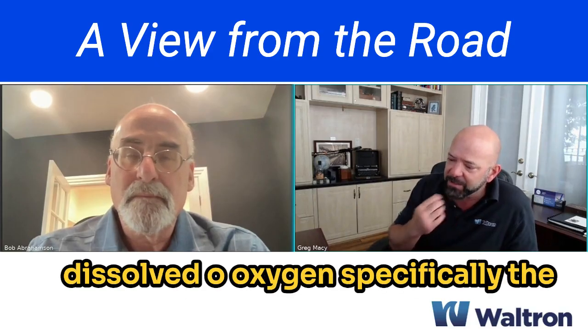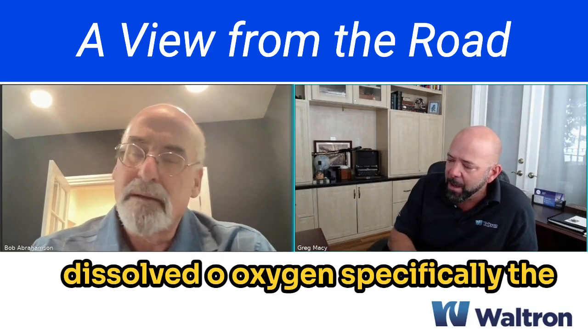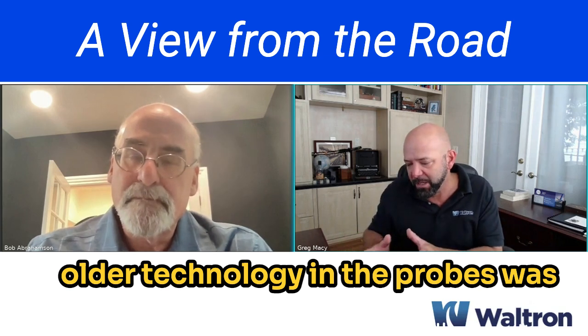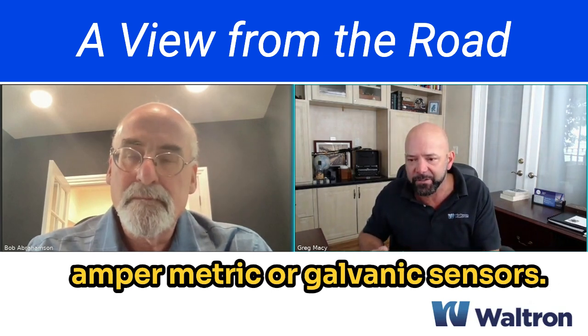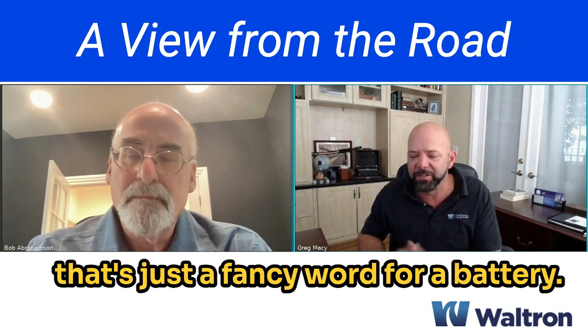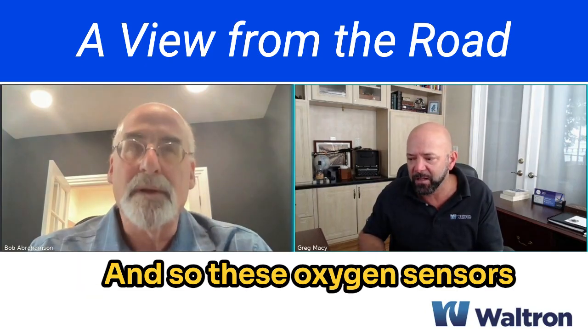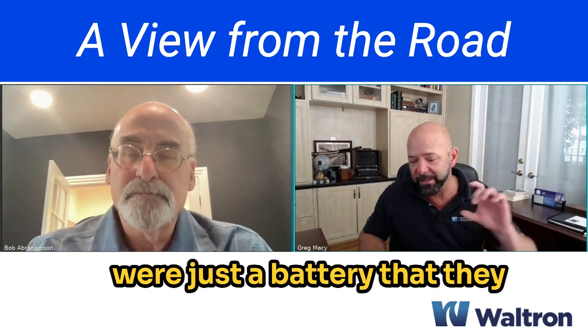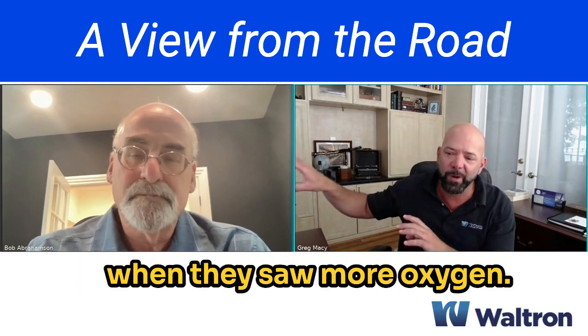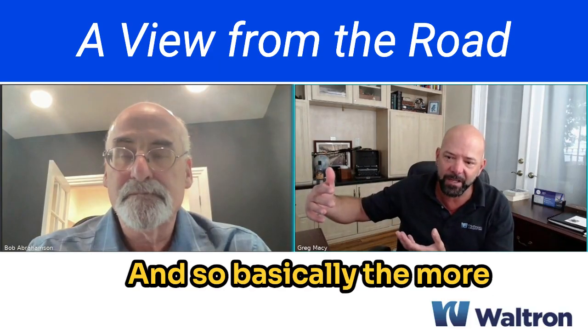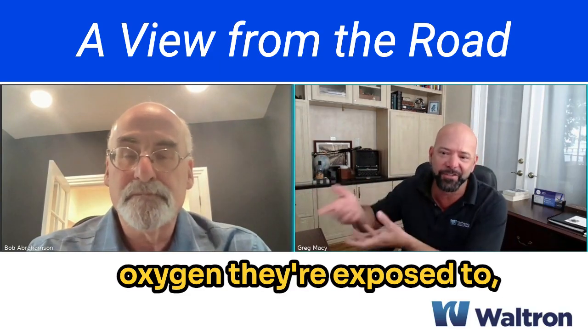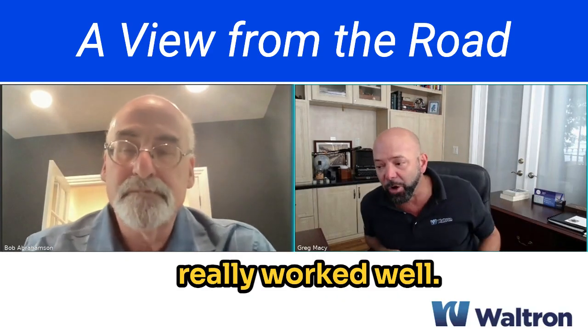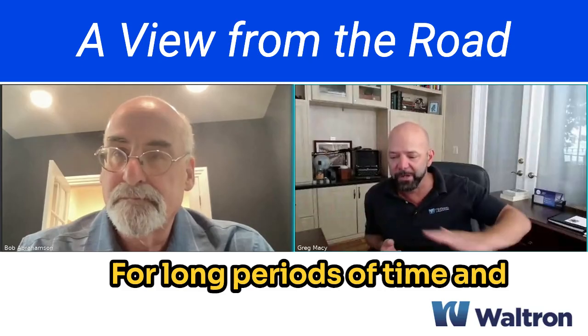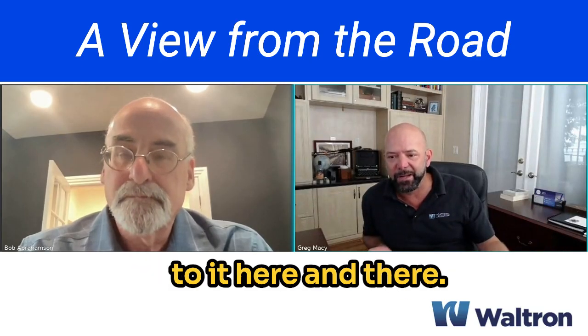And when we're talking about dissolved oxygen specifically, the older technology in the probes was amperometric or galvanic sensors. And what that basically means is that's just a fancy word for a battery. And so these oxygen sensors were just a battery that would produce more current when they saw more oxygen. And so basically the more oxygen they're exposed to, the faster the battery dies. And so that technology really worked well for long periods of time. And then they were exposed to it here and there.